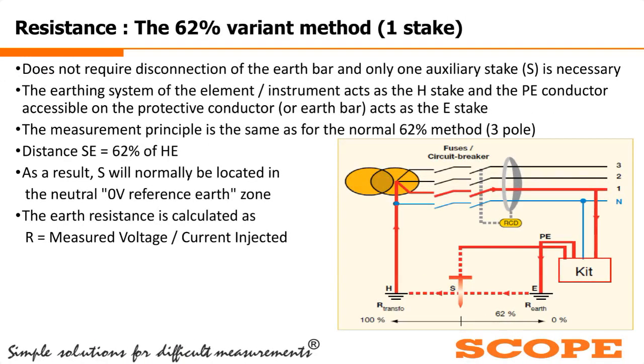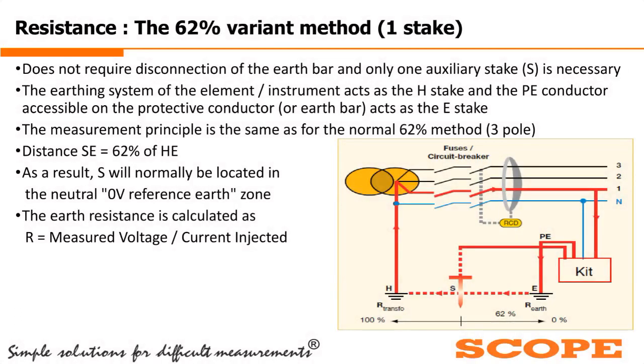Next method is the single stake method, or the 62% variant method. So in this single stake method, only one auxiliary stake S is used for the earth resistance measurement. So in this method, as in this connection diagram, we can see that the S terminal is used. So in this diagram, we can see that only one auxiliary spike is used, and this existing H stake, whatever the earthing of the instrument is available, will act as an H stake for the measurement of the earthing resistance, and the protective earth conductor will act as an E stake for the measurement.